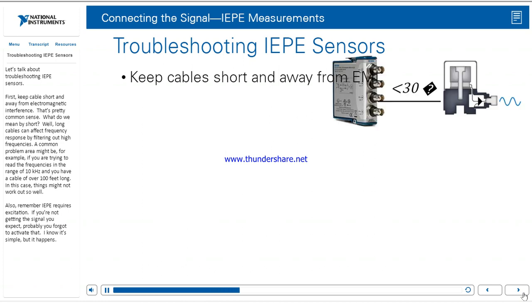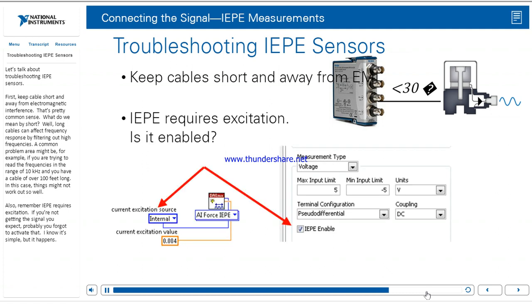Let's talk about troubleshooting IEPE sensors. First, keep cables short and away from electromagnetic interference. Long cables can affect frequency response by filtering out high frequencies — so if you're trying to read frequencies in the range of 10 kHz and you have a cable of over 100 feet, things might not work out well. Also remember, IEPE requires excitation. If you're not getting the signal you expect, you probably forgot to activate that — it's simple, but it happens.